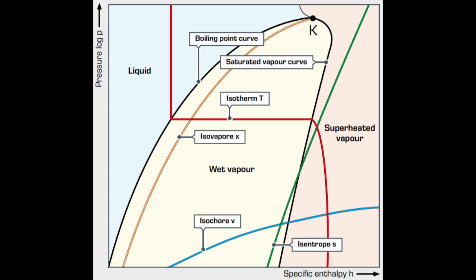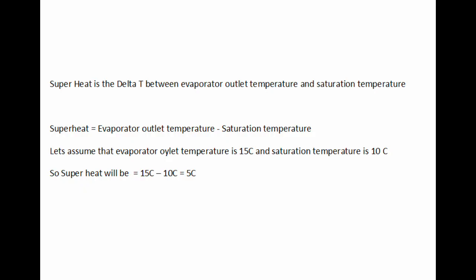Once you have these two values, you can calculate the superheat using the following formula. Superheat is the delta T between evaporator outlet temperature and saturation temperature.